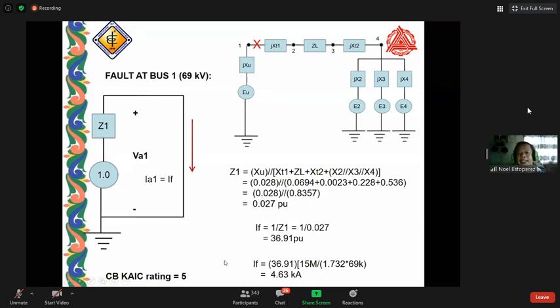Computing this, we will get a fault current of 36.91 per unit, which will be multiplied by the base current. The base current is the base MVA divided by 1.732 times 69 kV. We can get 4.63 kiloamperes. Now for the minimum, we can select a 5 kiloampere circuit breaker rating. So that is what we see for a fault looking at bus 1.